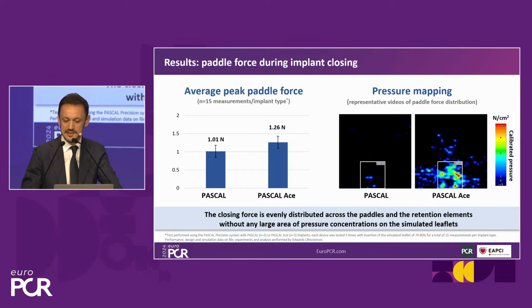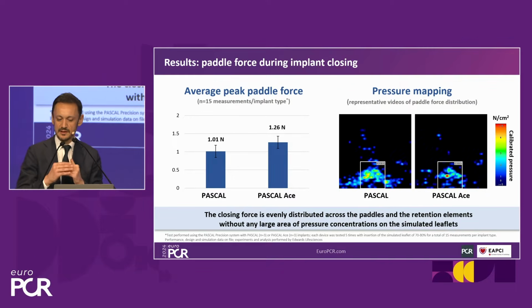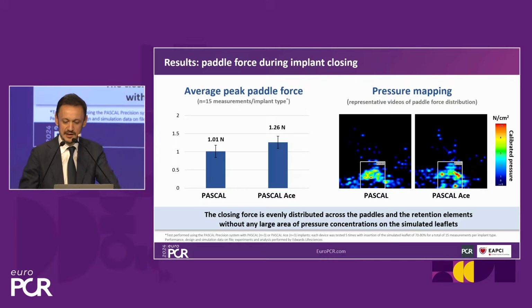The closing force is distributed across the paddle, on the surface between the paddle and the leaflet and the retention element, without any other area of pressure concentration. So it's really uniform and there are no different areas where the force is located. It's really concentrated only where the paddle and the clasp are in contact with the leaflet. Again, with no difference between PASCAL P10 and PASCAL ACE.